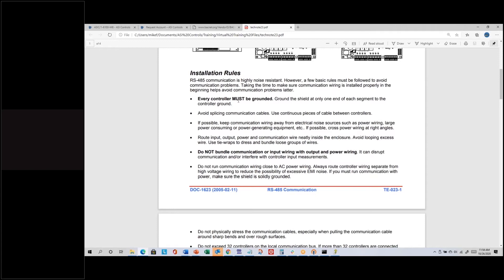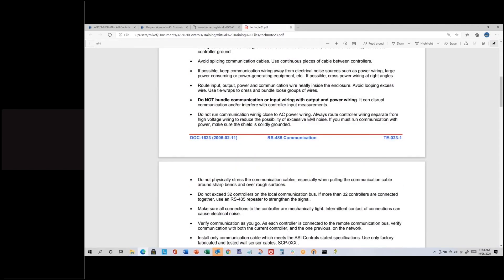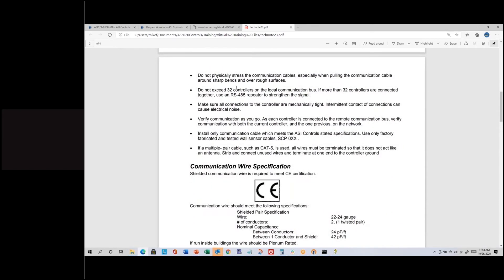There's other useful general RS-485 information in here. Make sure every controller is grounded, because for communications we're varying DC voltage on the plus and minus wires referenced to ground — if controllers have ground references much different from each other, that can affect communication. It also recommends not running communication wiring close to AC power, but if you do, use shielded wire. There's a mention about not exceeding 32 controllers on any RS-485 bus — it really should say 32 loads, since each of our controllers is a full load device.